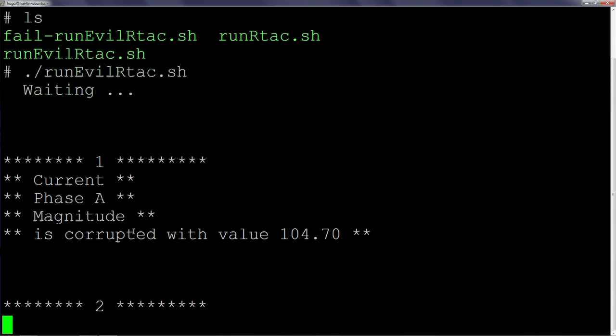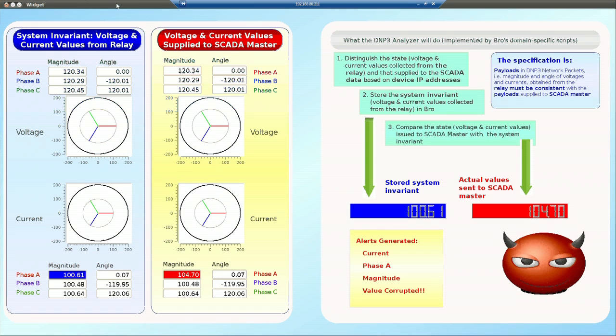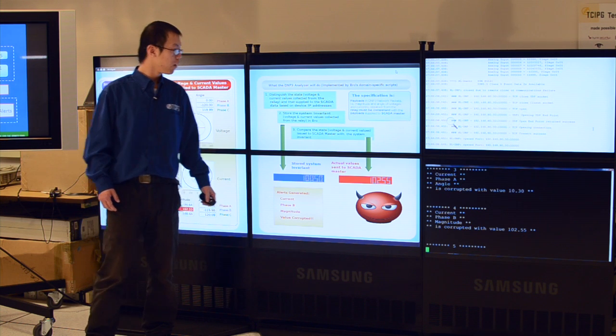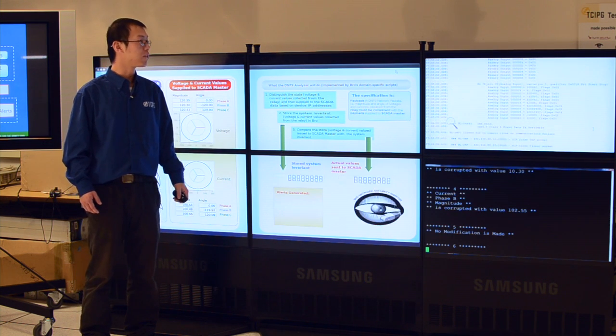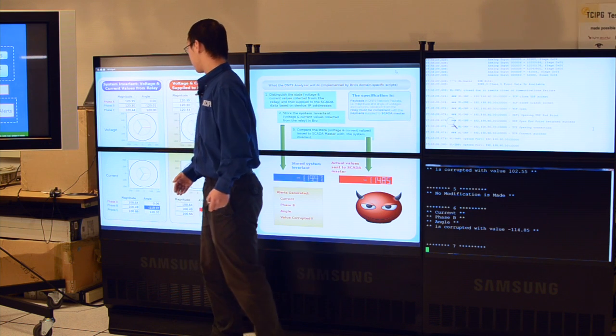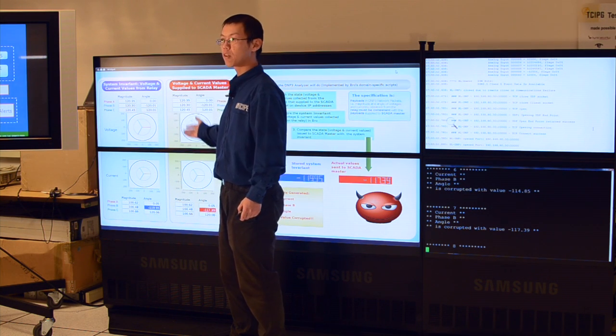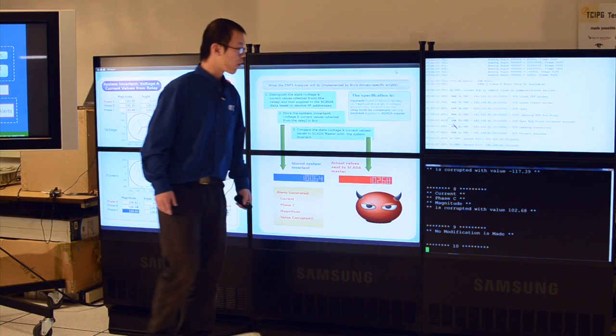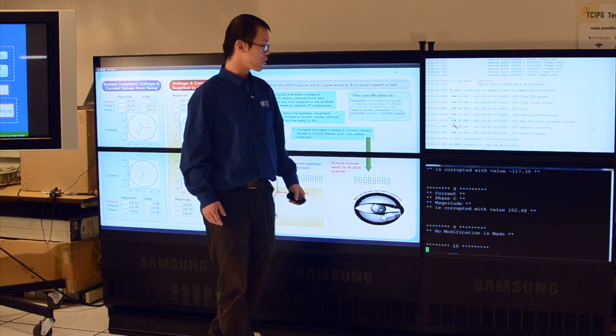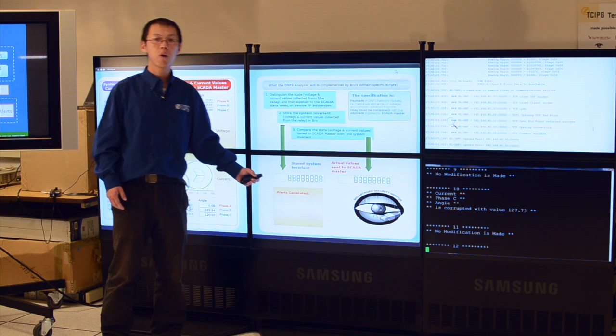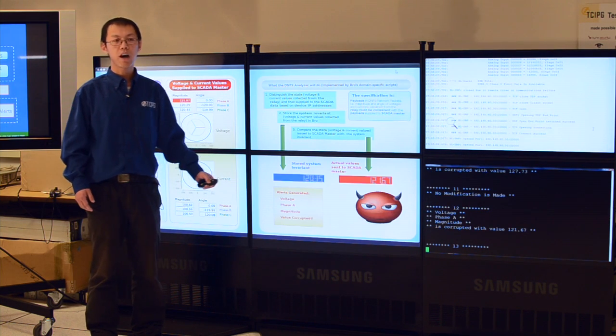By running this malware, we can see that our DNP3 analyzer begins detection as soon as the Trojan begins execution. In the blue box, we show the system invariant values. In the red box, we highlight the corrupted values. And in the yellow box, we display the detailed alerts. As we can see, we made minor changes to the corrupted data, so there are no obvious changes based on the values themselves. However, our DNP3 analyzer can make a successful detection. Also, from the RTAC screen, I programmed the Trojan to print out whatever it modified. By comparing the detailed alerts generated from my DNP3 analyzer, we can confirm that our IDS can actually locate the exact values that were corrupted.